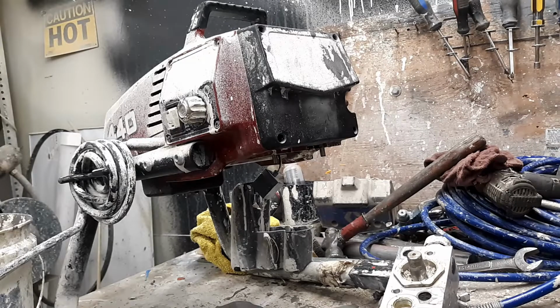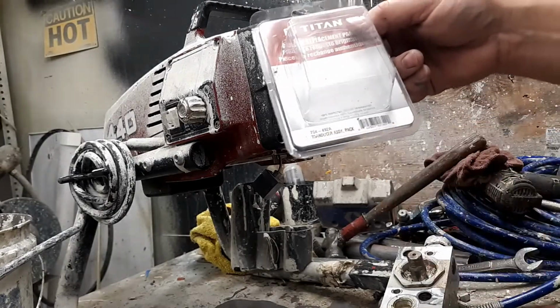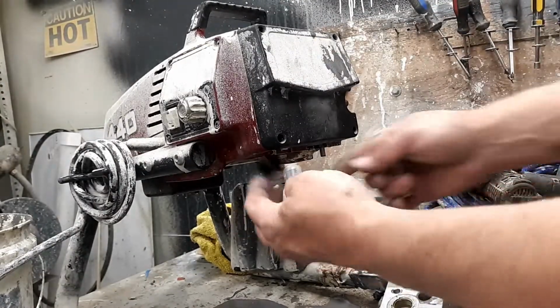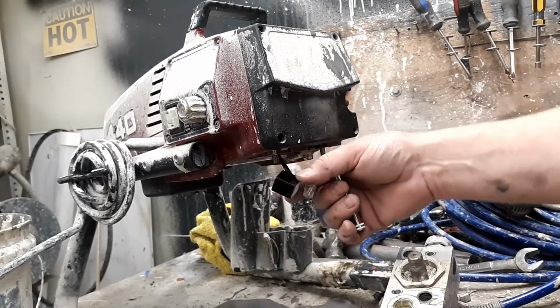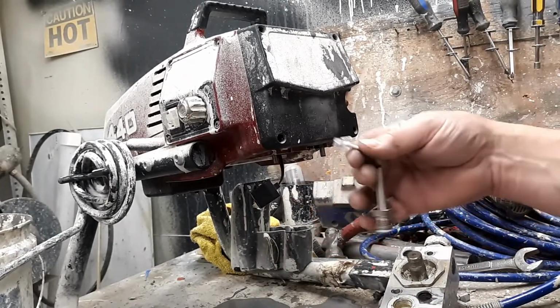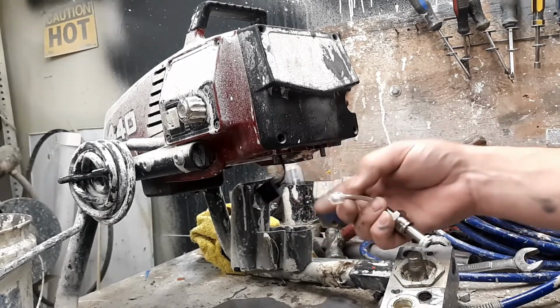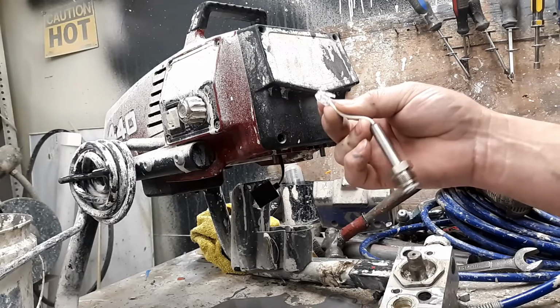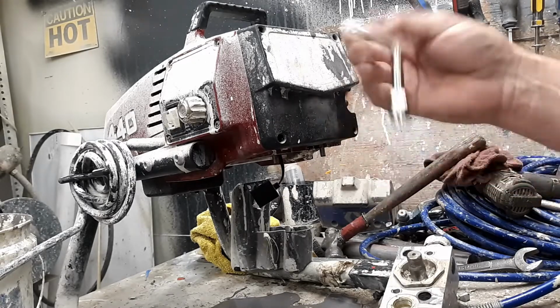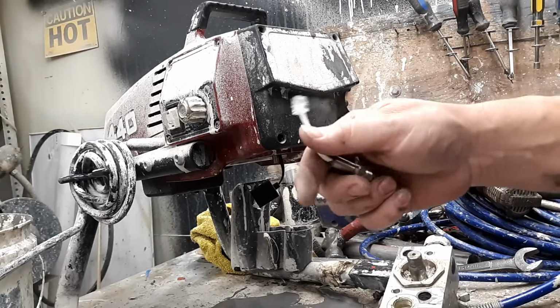On the 440, 540, 640, 740, 840, 940, 1040, and so on, they all use the same type of transducer. In this case, this is the short wire — it's a 704 492A, but it also has a jumper. Some of the bigger machines, 640, 740, 840 and up, have a jumper, or this wire may actually be longer. If this wire is longer, it's actually a different number, but it's the same transducer, just with a different length wire on it.